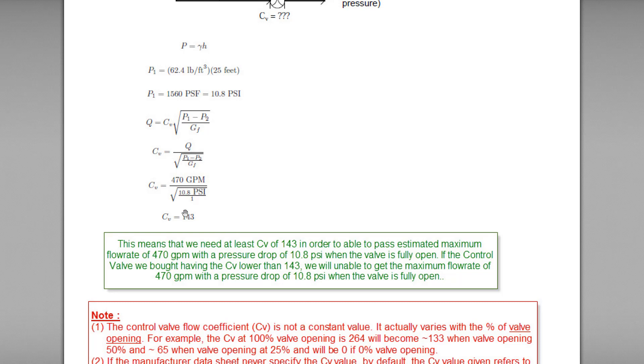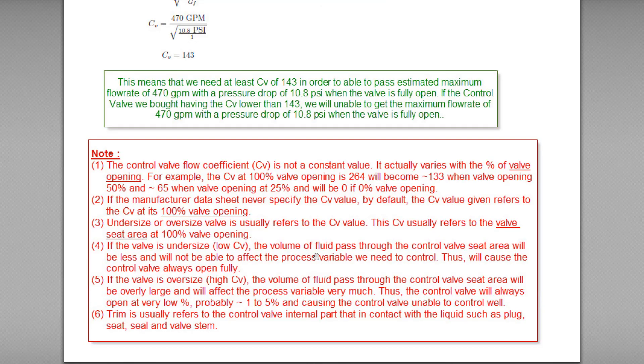This means that we need at least CV of 143 in order to pass estimated maximum flow rate of 470 gallons per minute with a pressure drop of 10.8 PSI. If the control valve that we bought having the CV lower than 143, we will be unable to get the maximum flow rate of 470 gallons per minute. That's all. Thanks.